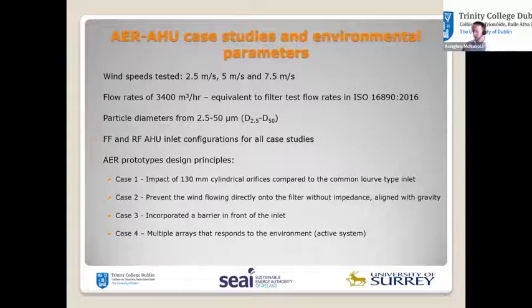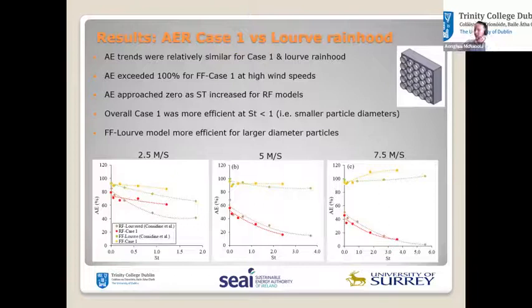So what were the findings? For the first case, there wasn't an enormous difference between this and the louver design—slightly better performance, but the same general trends. The yellow and green lines, for example, for an ambient wind speed of 2.5, show the aspiration efficiency starting closer to 90%, whereas earlier it was more like 95. The same general trend held when the wind is coming from behind the air handling unit, where we have a much lower concentration entering.